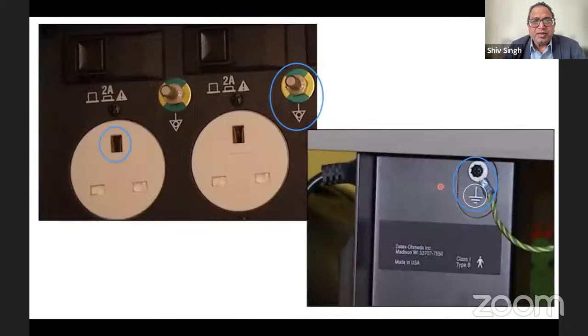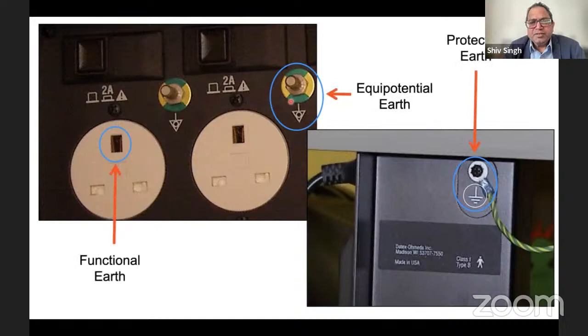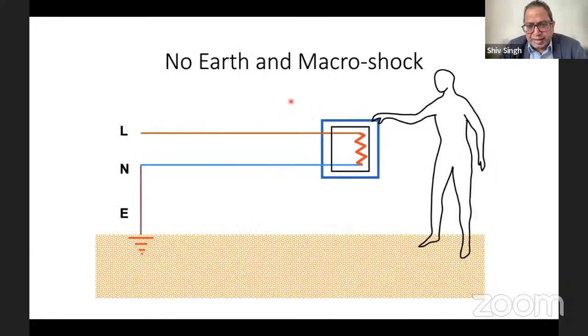If you see the blue circle there, that's your functional earth. That's the equipotential earth. And here there's an earth wire connected to the body of the machine, and that is the protective earth. So this is a protective earth, functional earth, and equipotential earth. Just labeling them. I explained to you how no earth can lead to macro shock. If there is a leakage of current, bodies become hot, you touch it, you will get a shock, depending on how much current is leaking.